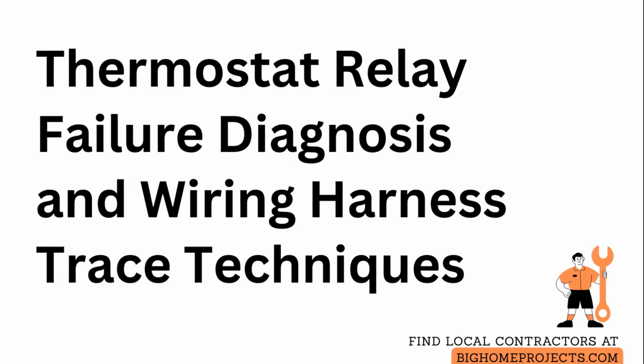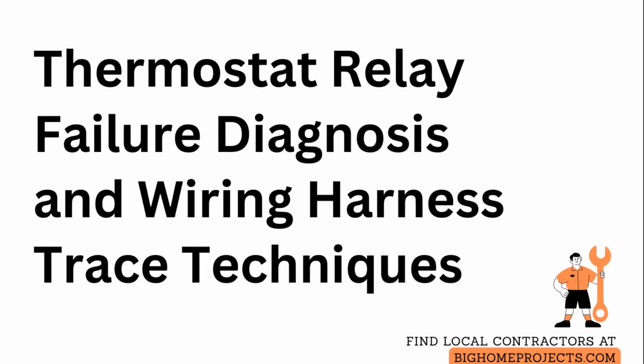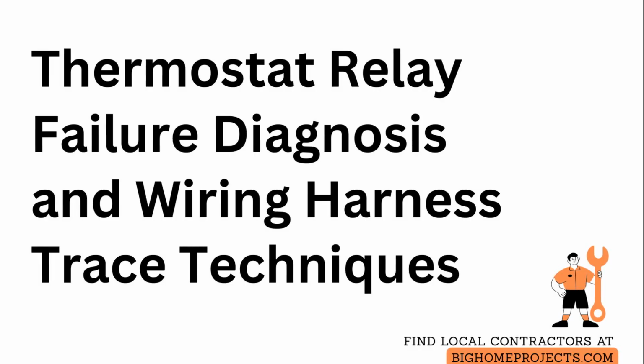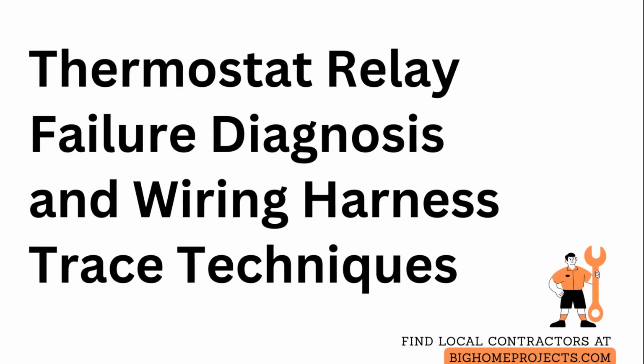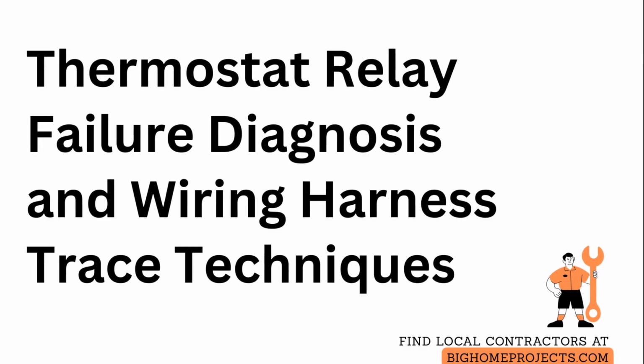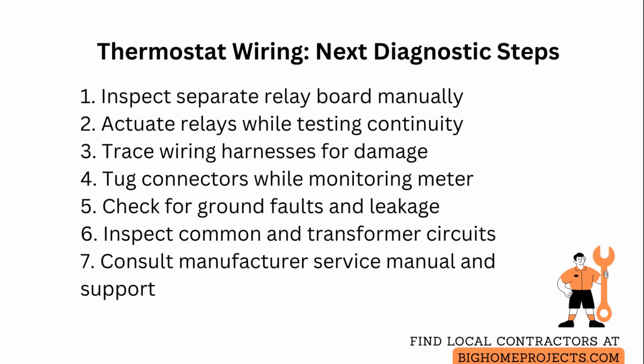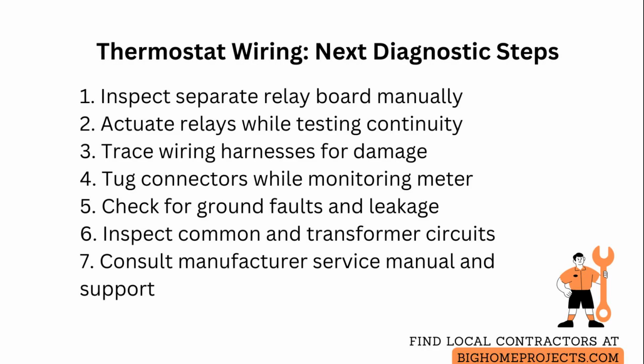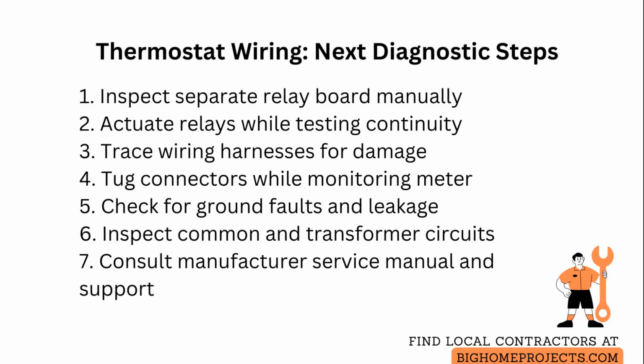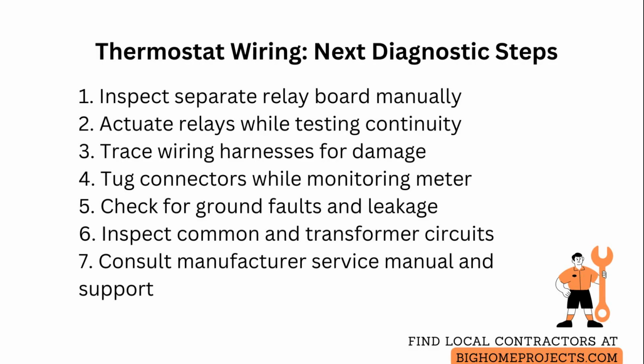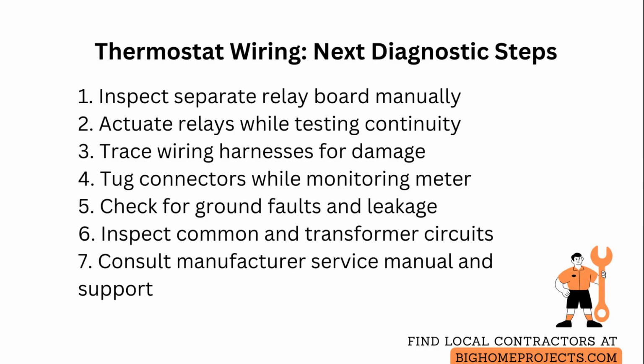If all thermostat wires check out and the control board is not the issue, the next steps focus on less obvious electrical and system-level faults that interrupt signals between the thermostat and the equipment. Start by inspecting the relay board if your system has one separate from the main control board. Relays can stick or have welded contacts that appear fine visually but fail under load, so actuate each relay manually while monitoring continuity with a multimeter set to the appropriate range.